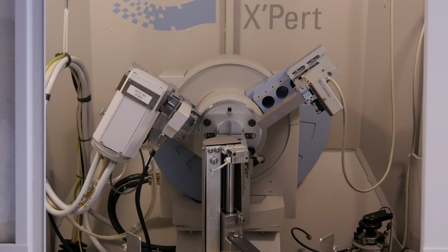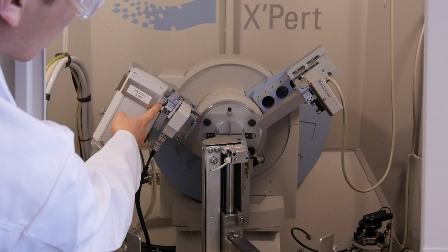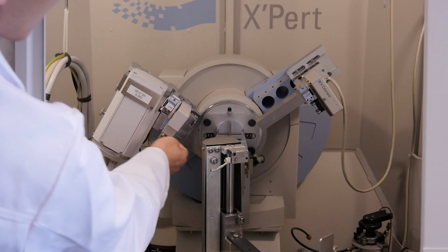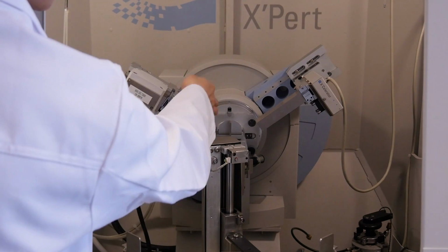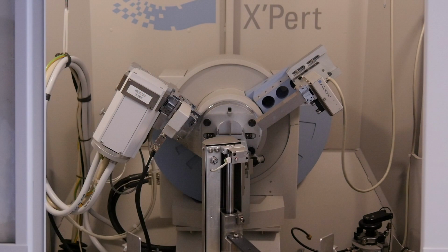A typical laboratory X-ray tube is working at 45 kilovolts and 40 milliamperes. Unfortunately, the life of the tube is limited because of the decay of the intensity, typically 10% per year. X-rays pass through a set of optics onto the sample, then are collected by the detector. The K-beta filter, namely the nickel filter, is used to remove the K-beta radiation.